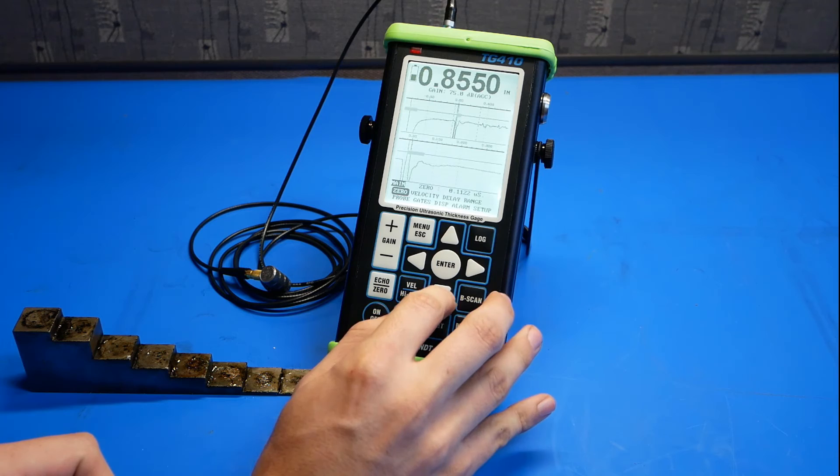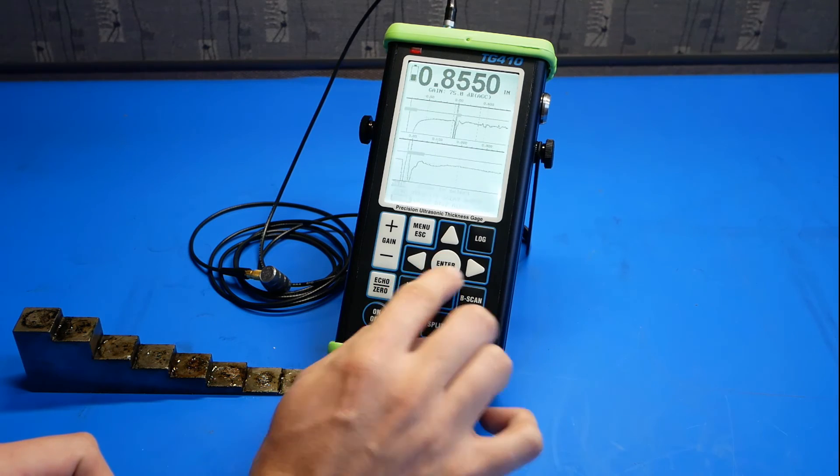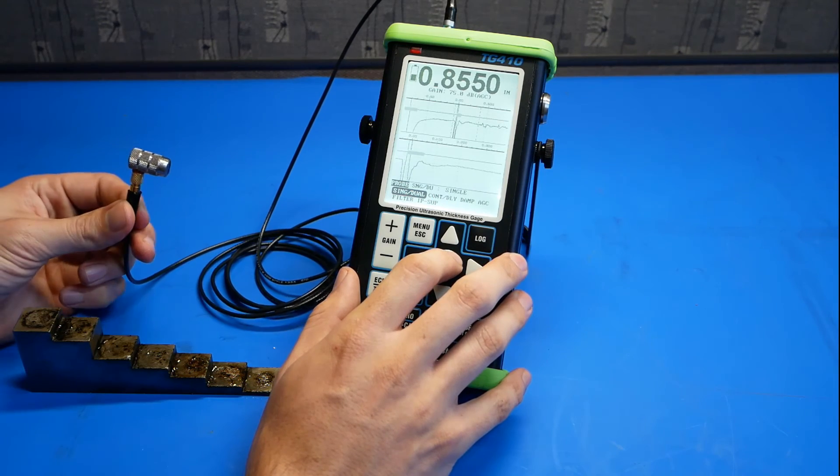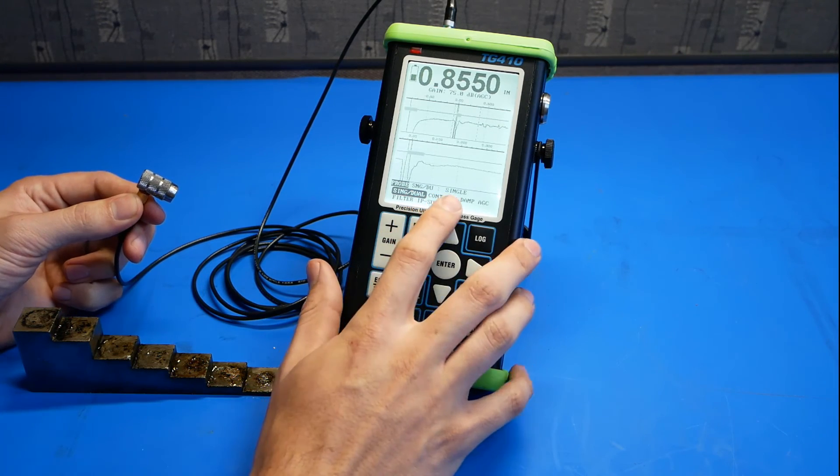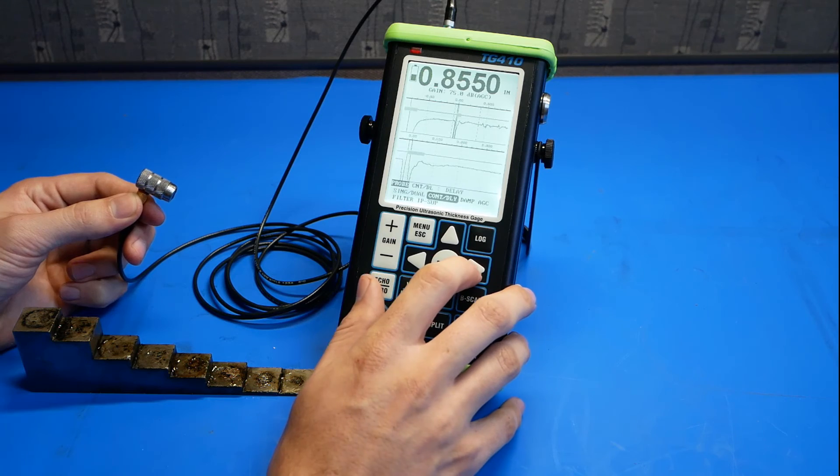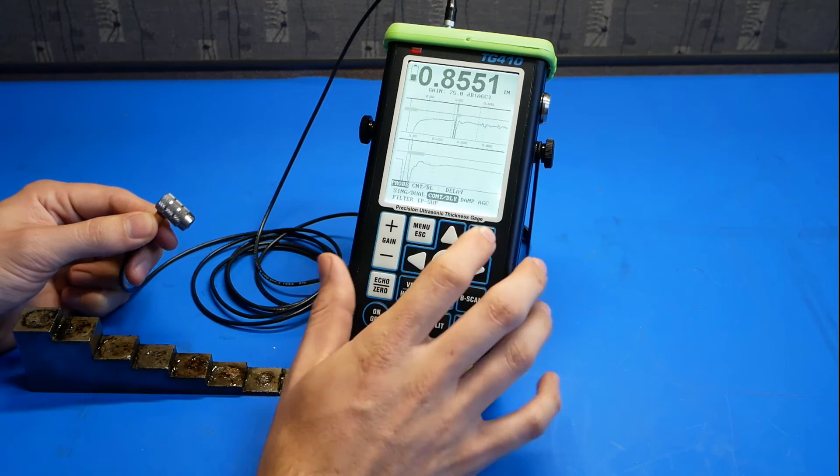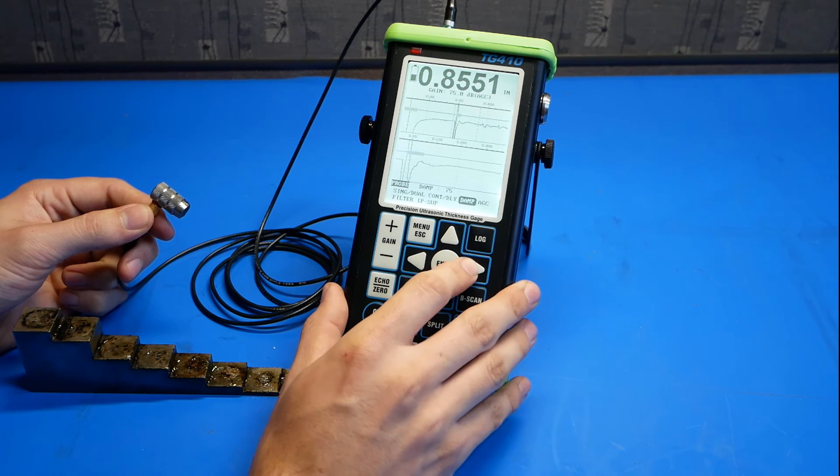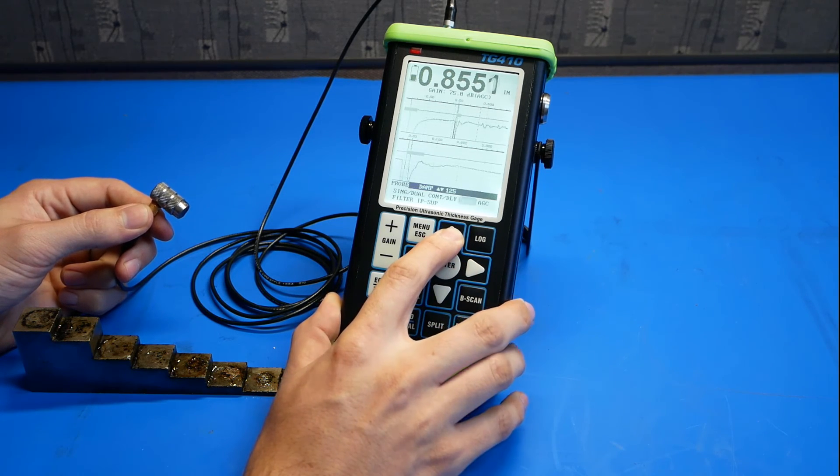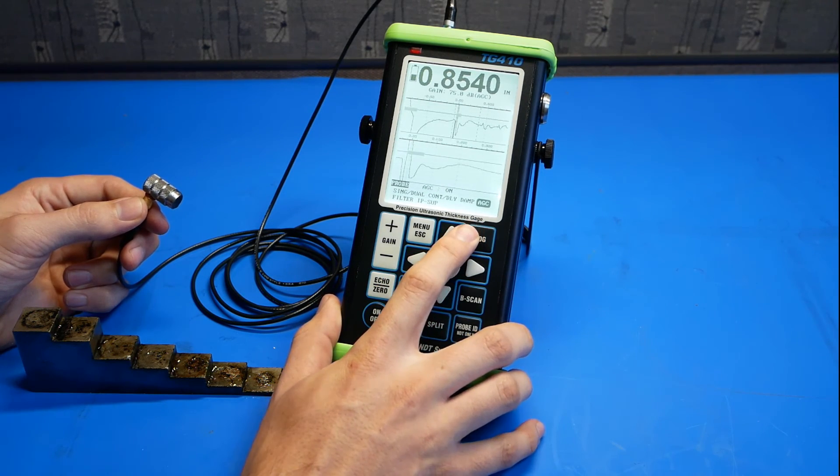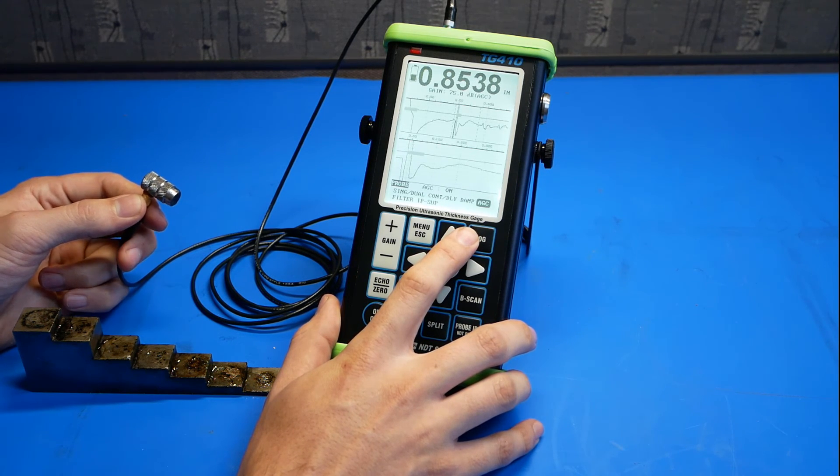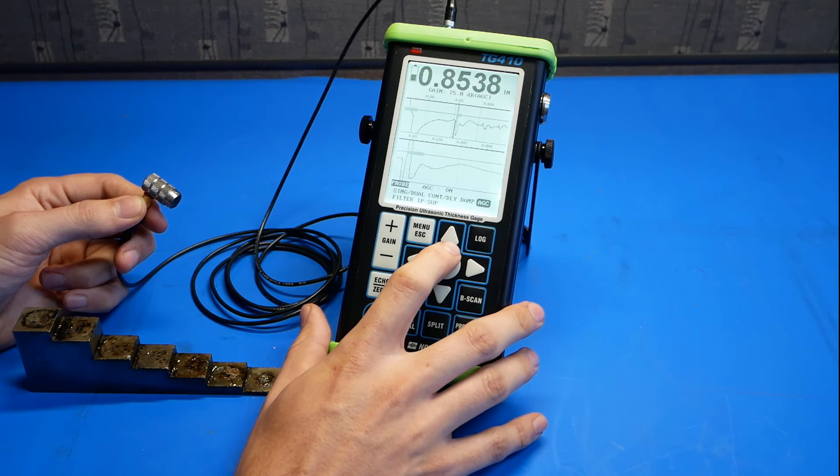To do this, we'll go to probe. Select single or dual element. Since the D11 is a single element delay, do single. Contact or delay. This is a delay line, so we'd select delay. Damping is fine tuning for the waveform. We have automatic gain control. This will boost the signal up until it reaches at least 80% screen height.